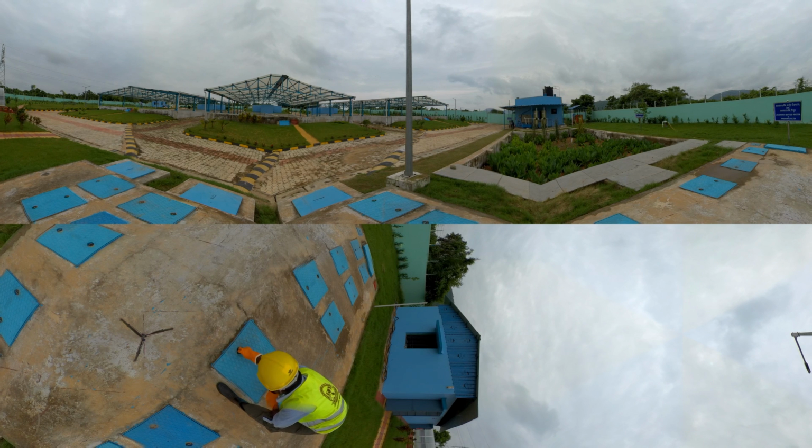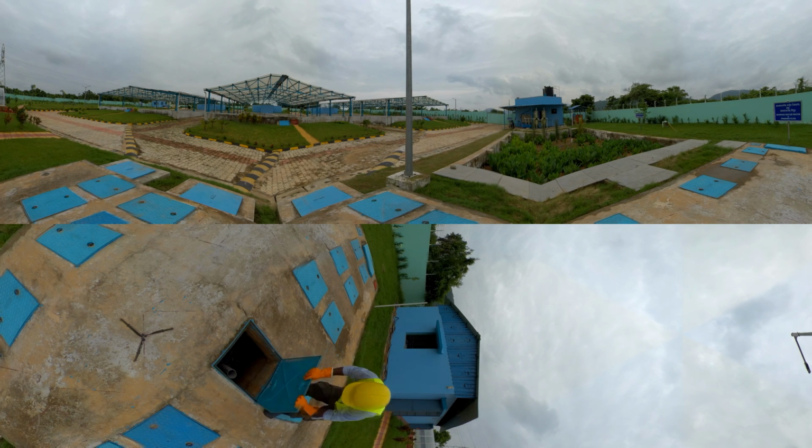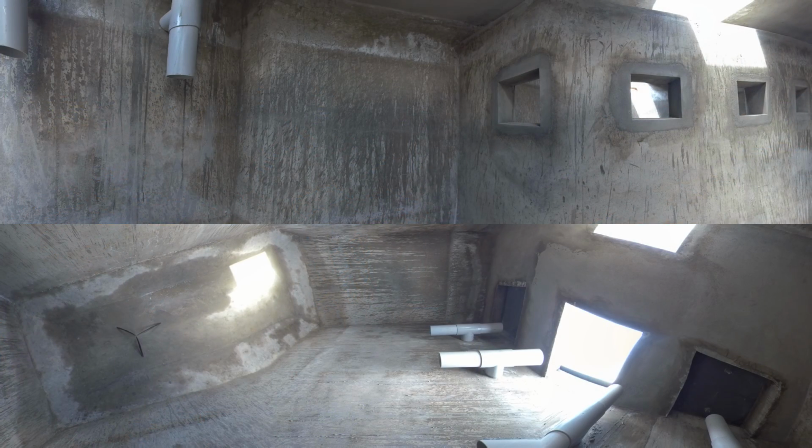Operation 2. Once in a month or if there is a bad odor around the system, you should check the vent pipe for any external damages or blockages. You can check by looking into the pipe or tapping it with a stick. Please use the L brush to remove the blockage. If there is external physical damage to the pipe, you should order a replacement.